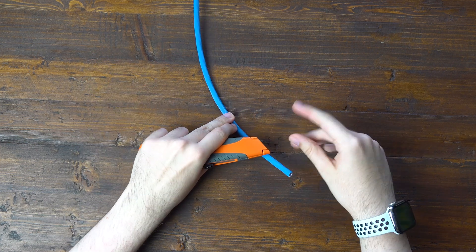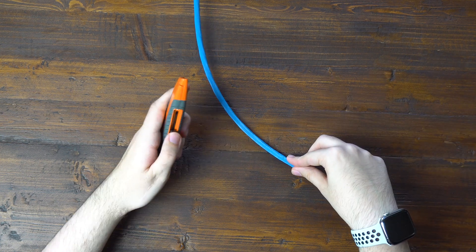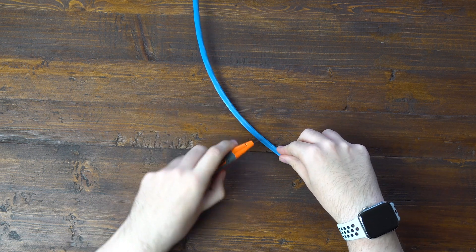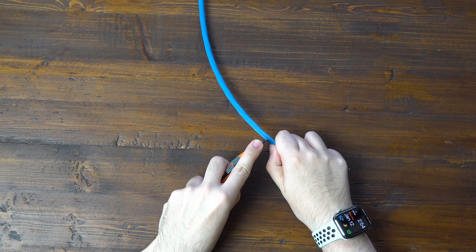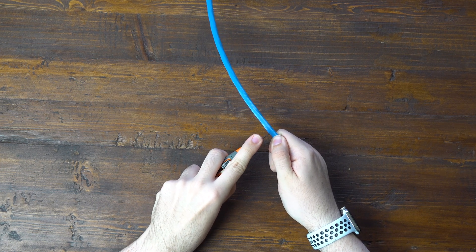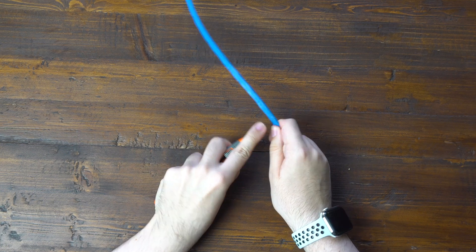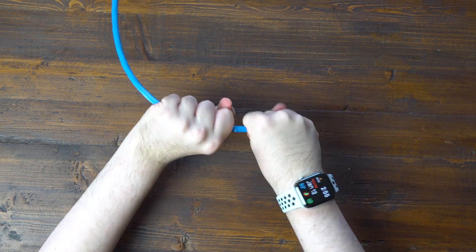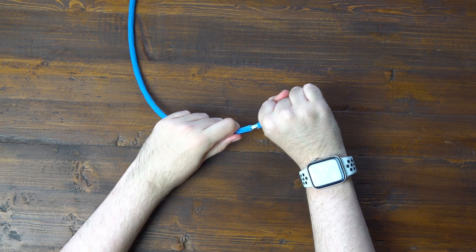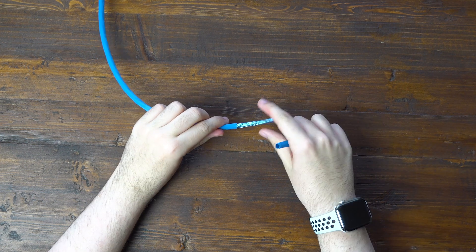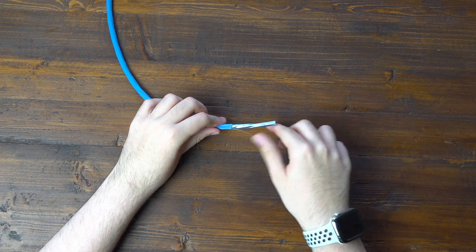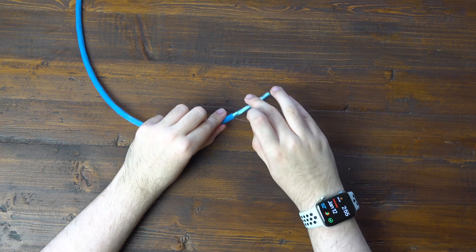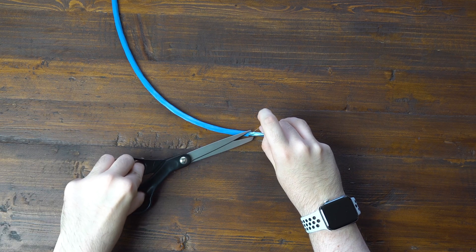Standard practice is to do about 2 inches. I like to do a little bit more in case something's on the tip of the wire that may be broken. So I do a little bit over 2 inches. It is really easy to work with longer cables than shorter ones. So what we'll do is we'll just take our knife and just very carefully cut through the casing on here. And once we do get through that, we'll just go ahead and pull it right off. So once we do have the casing cut, the best way to do that is just to twist in opposite directions until you see that break, and then just pull right off. Now if you did it right, your foil may also come off, but I purposely don't cut it that deep. So if the foil doesn't come off that way, I don't have to ever worry about cutting the cable.